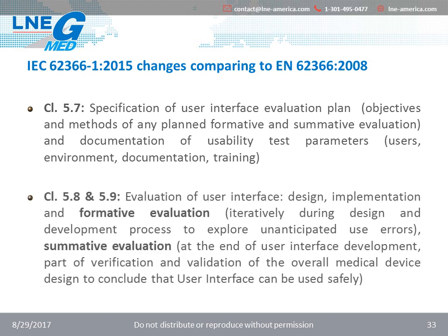And finally, Clauses 5.8 and 5.9 are about evaluation of user interface, design, implementation, and formative and summative evaluation. Please note that formative evaluation should happen iteratively during the design and development process to explore unanticipated use errors, while summative evaluation happens at the end of user interface development, which is part of verification and validation of the overall medical device design to conclude that the user interface can be used safely.